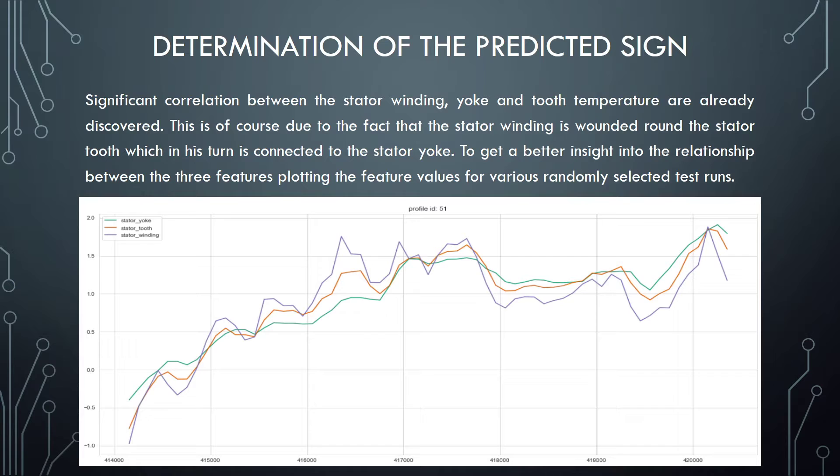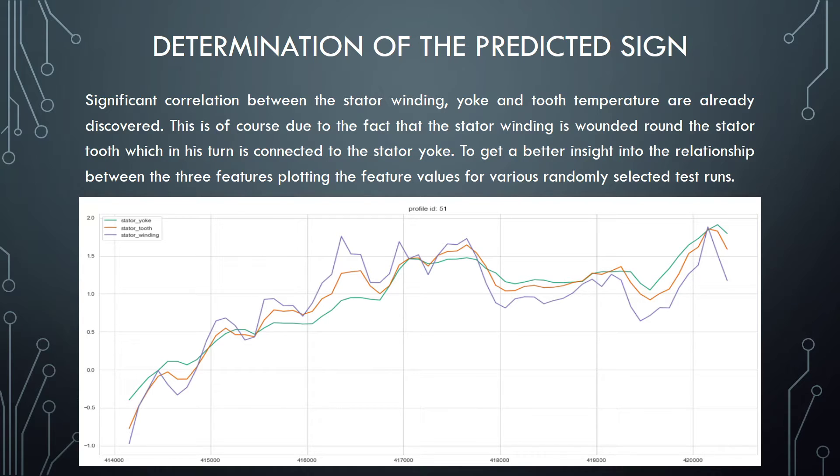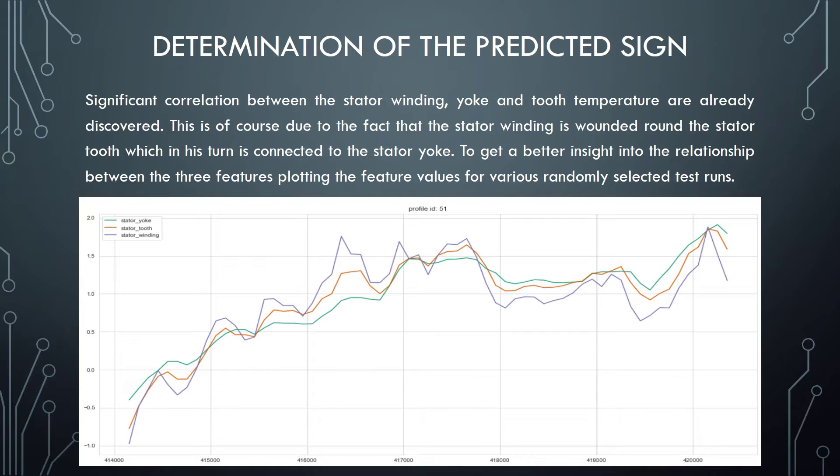Determination of the predicted sign. Significant correlation between the stator winding, yoke and tooth temperature are already discovered. This is, of course, due to the fact that the stator winding is wound around the stator tooth, which in turn is connected to the stator yoke. To get a better insight into the relationship between the three features, plotting the raw feature values for various randomly selected test runs.